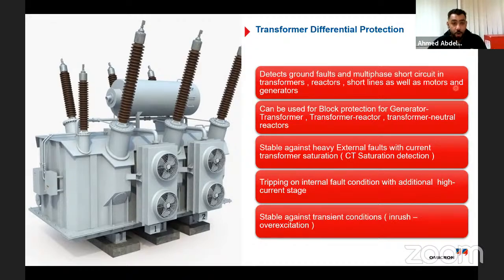But with every protected object, I need to understand the physics, the phenomena which will happen with this protected object. For a transformer, I have so many parameters that will affect the differential protection. I need to take them into consideration when I am setting this relay and when I am testing this protection. With reactors, I have another phenomenon: in the reactor, I don't have a low voltage side or a side 2, because it's just a coil connected to the ground to give a neutral point to the line. Short lines: there is no vector group, there is no phase rotation, there is no change in the current value due to the turn ratio of the transformer. Motor and generator, there is nothing to change. The current in equals the current out from the neutral side and from the line.